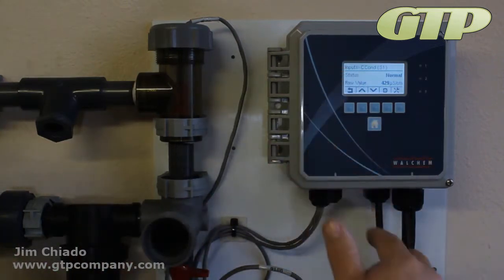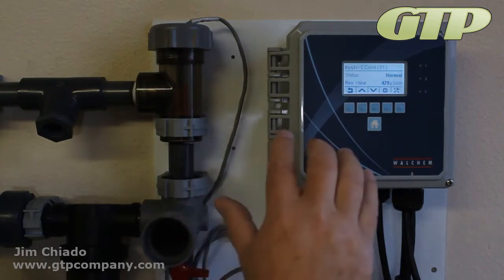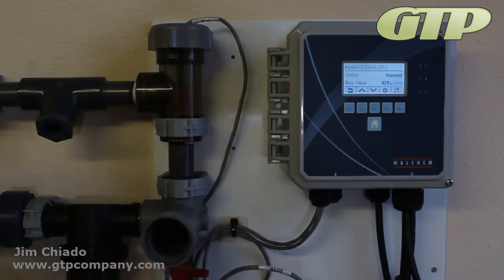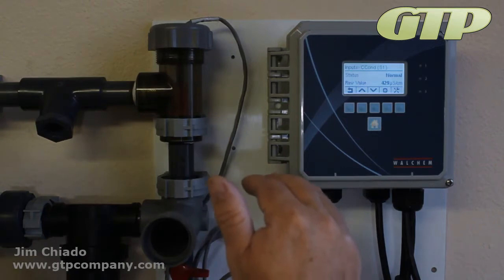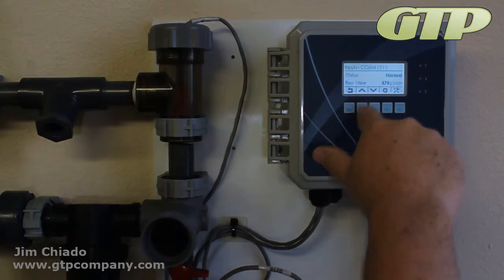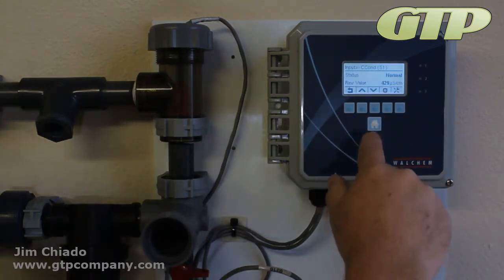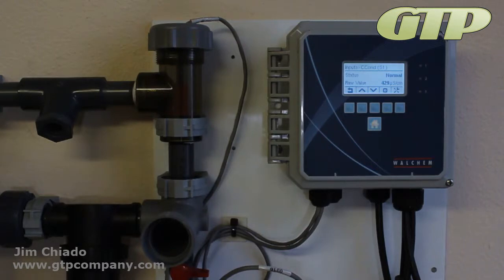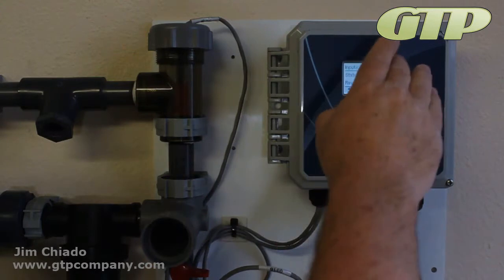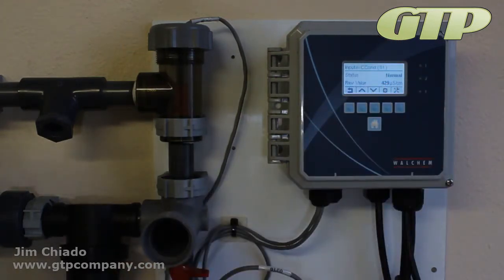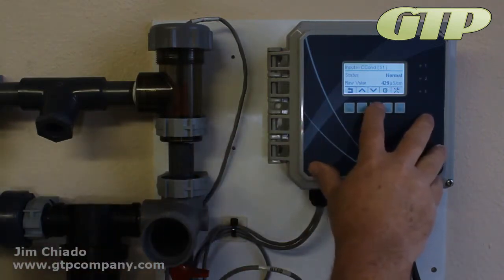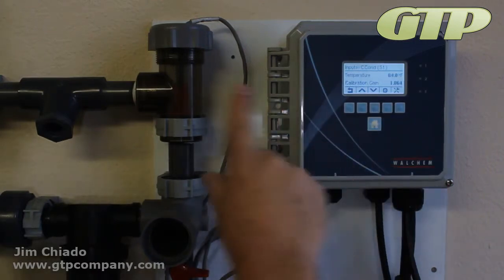Okay, if not, and you can see on occasion, you move it up, get it close, and then all of a sudden it goes out of range. That's because right now if we took this 429 times 1.5, we would see that we could only calibrate it so far, and if it's out of range, it's out of range. If you want to just get by until tomorrow, go as far as it will go at 1.5 times, calibrate it to there, go get a new one on order, which we always have in stock, and we'll send you one off and you can come out and redo that again. The raw value is the key to that.